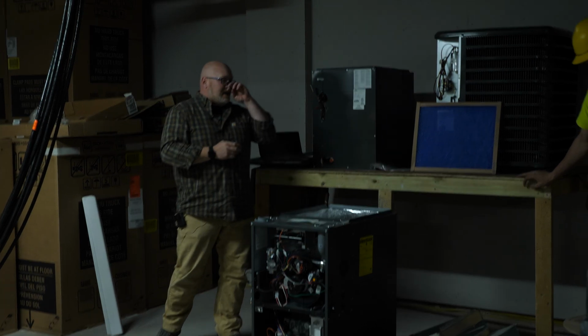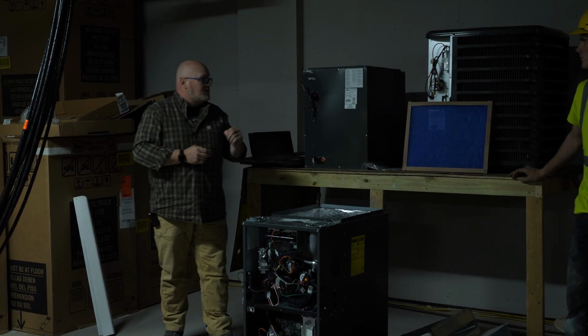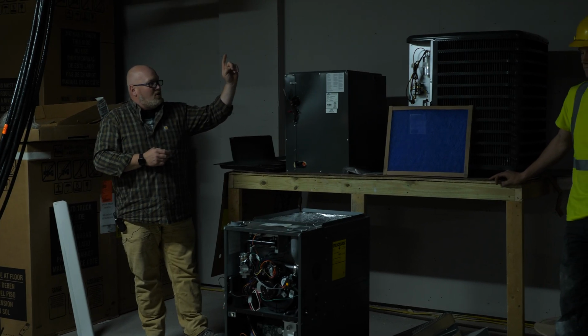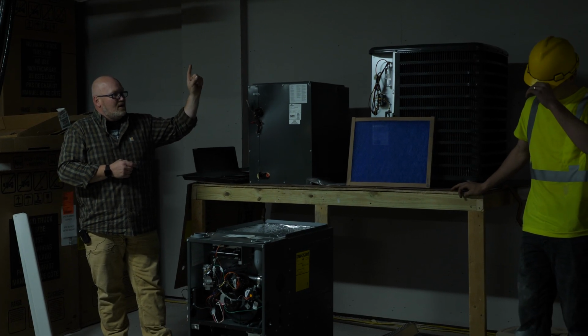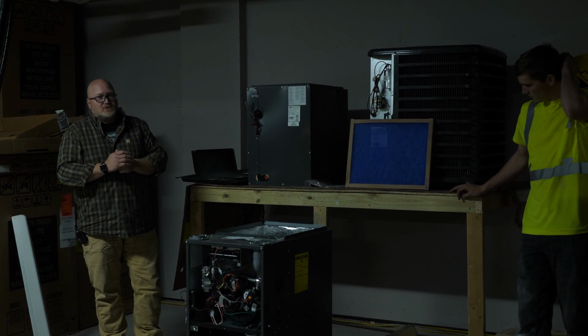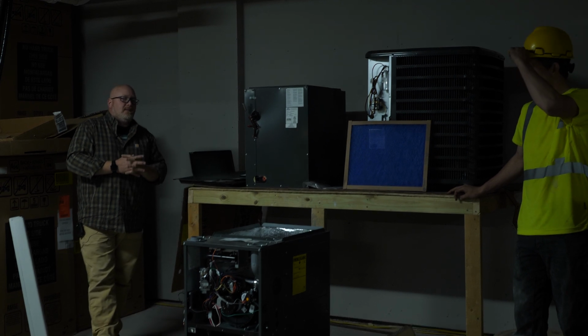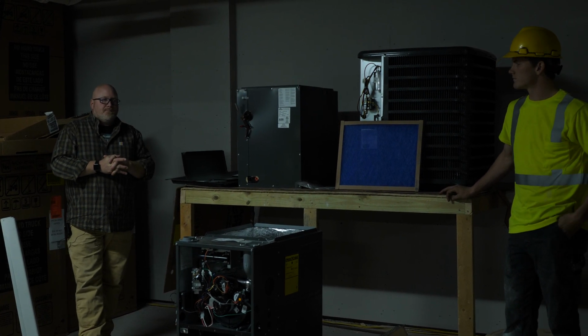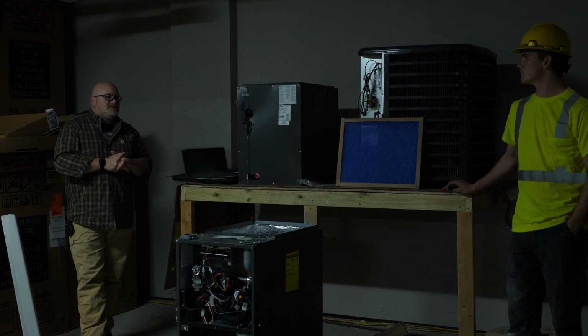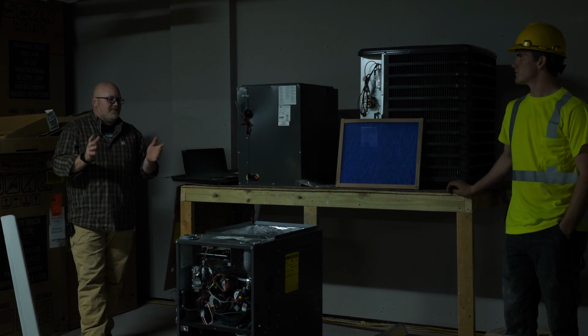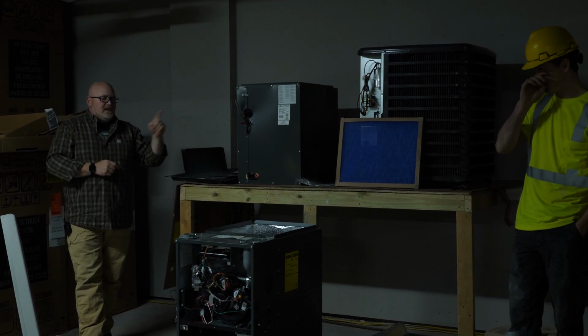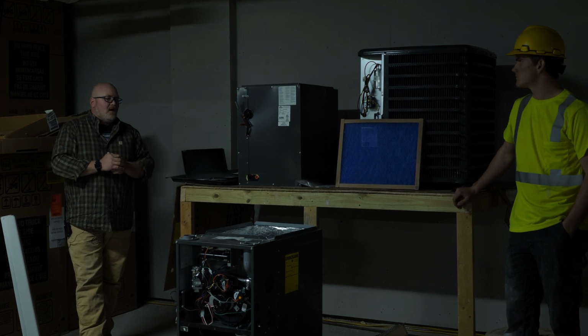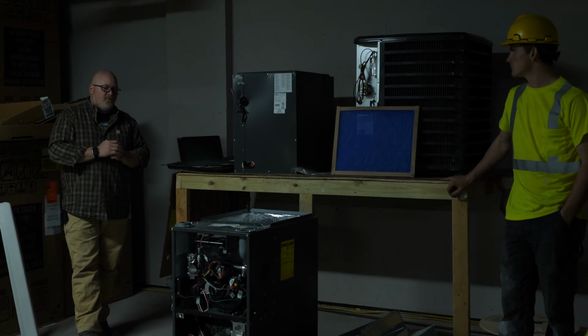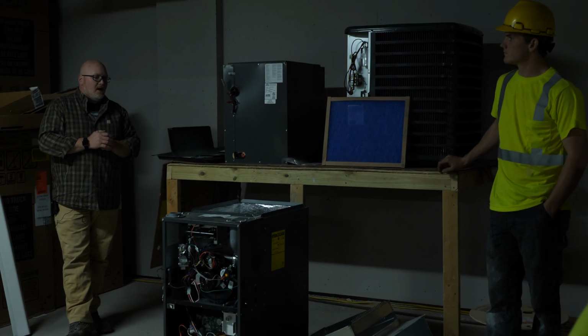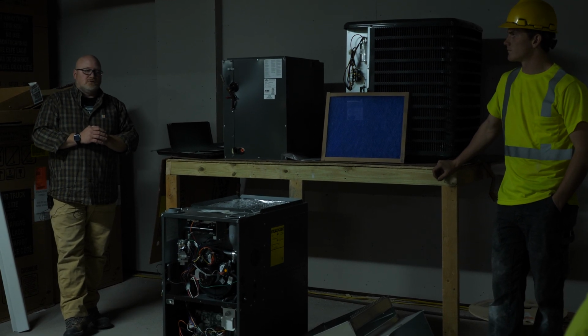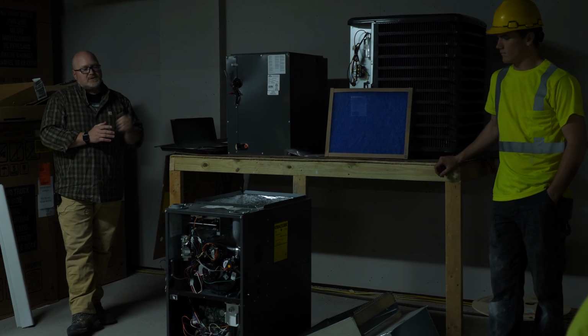Number 4 is going to take you outside to take a look at your contactor, your capacitor, and your condenser fan. So taking a look at these components in that order, you should probably be able, I would say within 50 to 60% of the service calls, take care of those items first. If you can solve those before calling a service tech, generally you'll be in good shape.